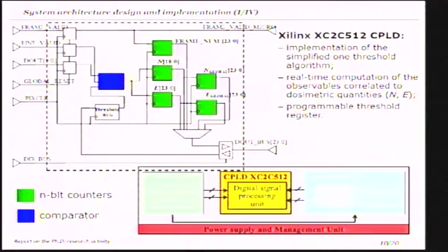This algorithm can be easily implemented in a complex programmable logic device (CPLD). The schematic diagram of the firmware consists of just one comparator with the absolute threshold and counters that collect the two threshold observables. We also use two global counters that collect the total amount of dose for each medical procedure, used at the end of acquisition to recover the wireless interface losses.